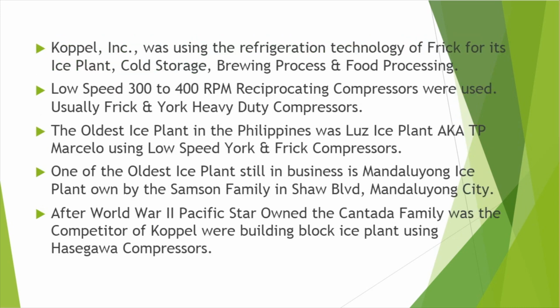Koppel, Inc. was using the refrigeration technology of Frick for its ice plant and cold storage and brewing process and food processing. Low speed 300 to 400 RPM reciprocating compressors were used, usually Frick or a York heavy duty compressor. It's a 2-piston compressor. The oldest ice plant in the Philippines was Luz Ice Plant, also known as TP Marcelo, using low-speed York and Frick compressors.